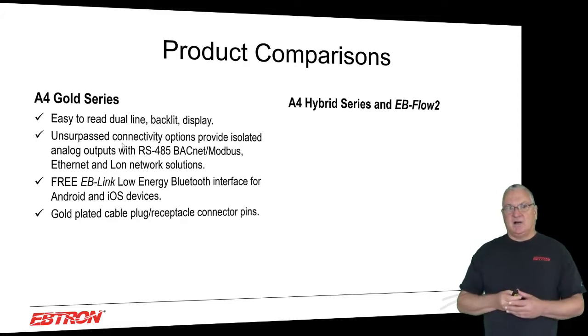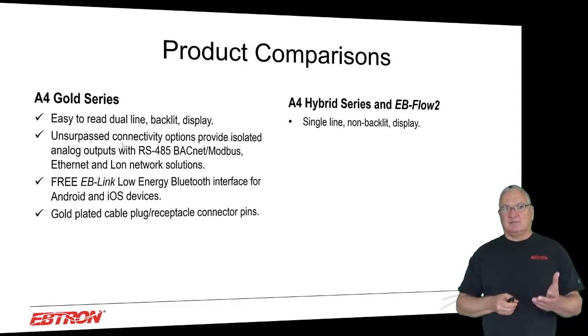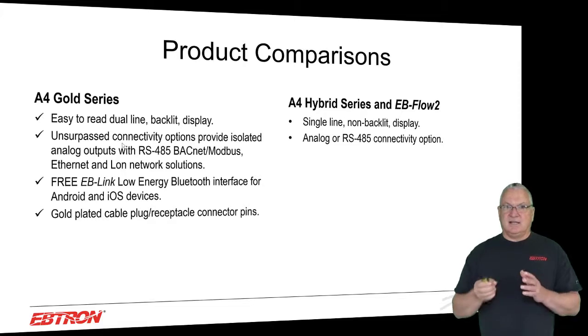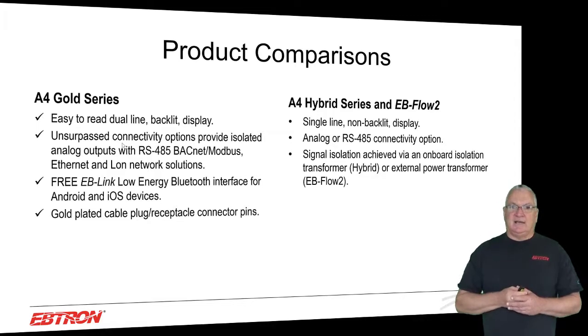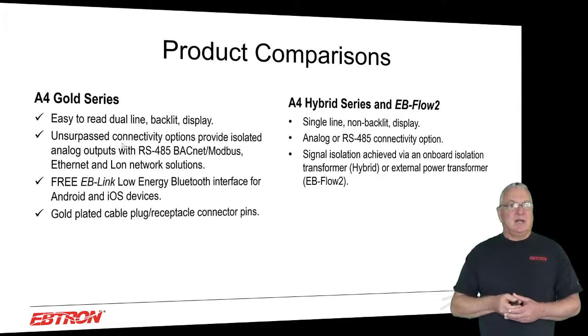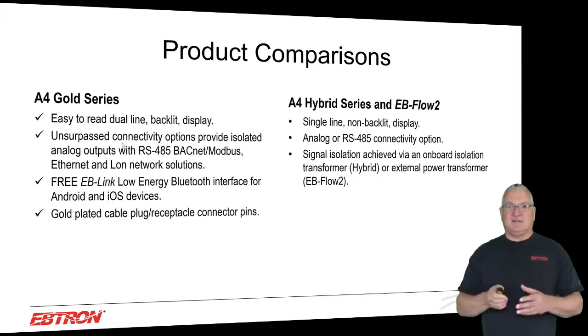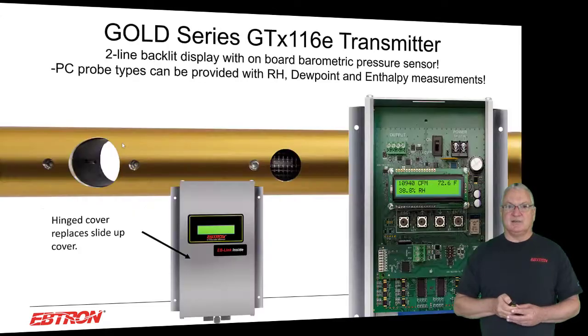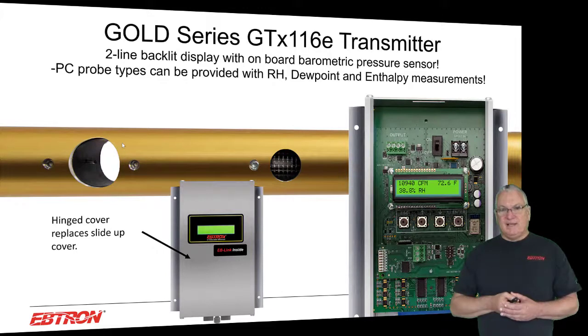When you look at the Advantage 4 Hybrid Series and EBFlow, which are our other products, they're a little bit lesser products, single line, non-backlit display on both. The connectivity options are less. It's either analog or RS-485. And the signal isolation is achieved via onboard isolation transformer on the hybrid, or with your external power transformer on the EBFlow 2. It's really not that much of a disadvantage, but it's certainly not the same as the Gold series.